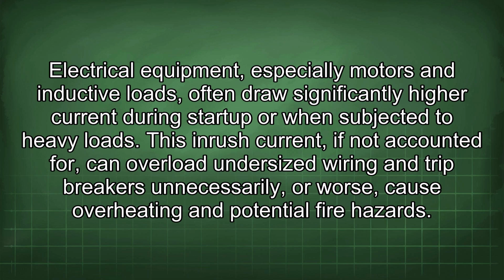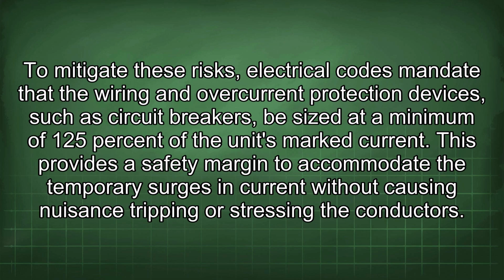This inrush current, if not accounted for, can overload undersized wiring and trip breakers unnecessarily, or worse, cause overheating and potential fire hazards. To mitigate these risks, electrical codes mandate that the wiring and overcurrent protection devices, such as circuit breakers, be sized at a minimum of 125% of the unit's marked current. This provides a safety margin to accommodate the temporary surges in current without causing nuisance tripping or stressing the conductors.